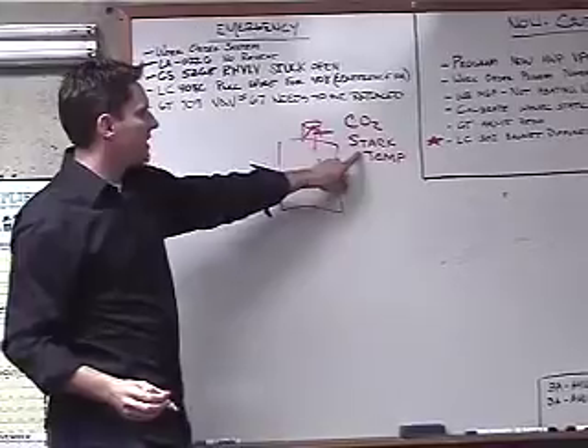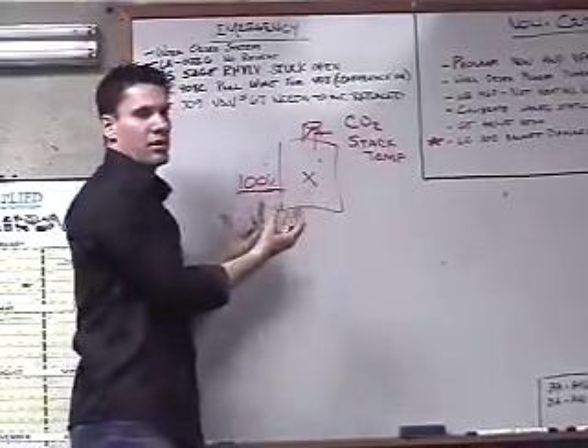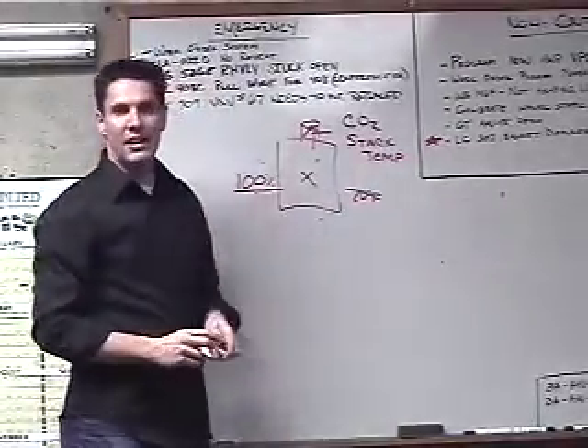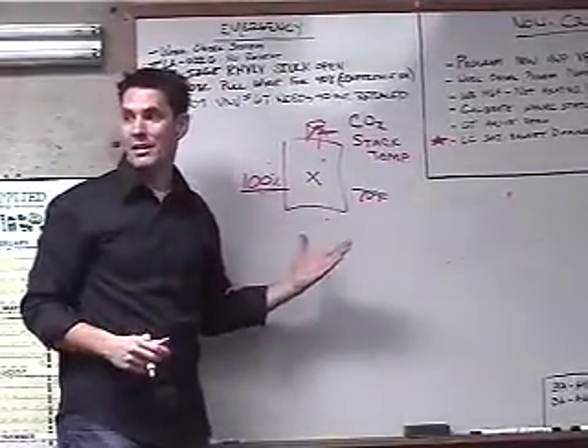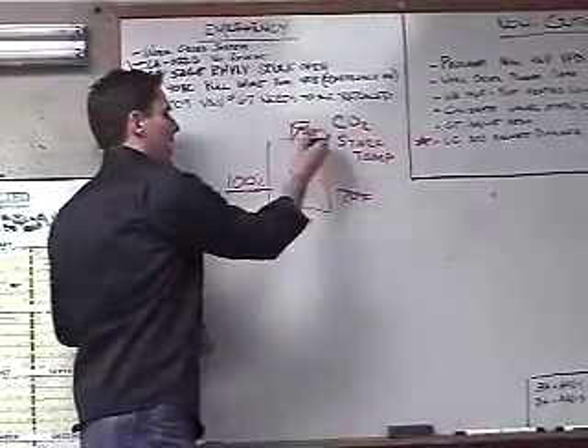Now, I've come up with my stack temperature, but we also have to look at what's our combustion air temperature. So if I'm pulling from the room and my room temperature is 70 degrees Fahrenheit, I would subtract that out of my stack temperature because my boiler didn't create that heat. That was already there. My boiler created the difference. Okay, and what temperature am I coming out at this point?